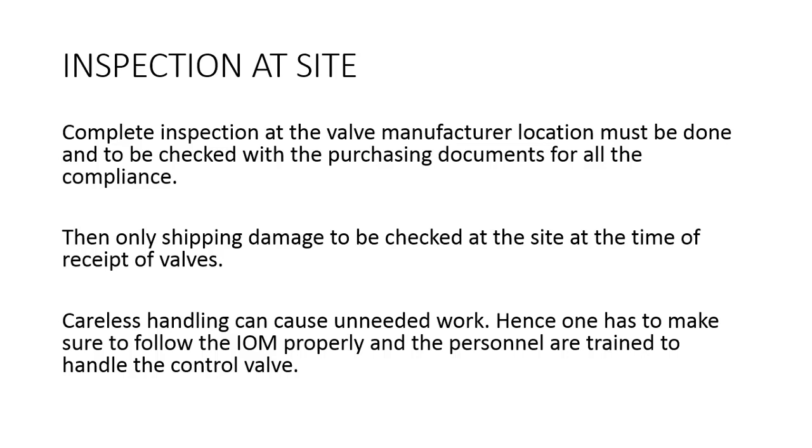Complete inspection at the valve manufacturing location must be done and checked with the purchasing document for all compliances. This can be done by appointing a third-party inspector or sending quality personnel from the end user side. Complete inspection might include dimensional check, visual check, all material test certification review, testing report review, pressure test witness, surface preparation for painting and painting test.